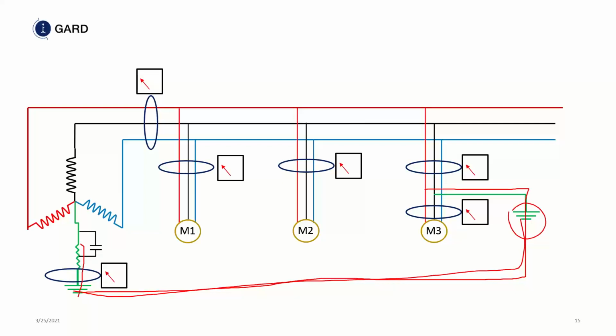That fault current only exists in this faulted path. So anywhere in that path, if we turn on the pulsing and we change the value of that resistor, we're going to see a fluctuation in the current if we put a 3-phase CT around all 3 phases of the system. We're going to follow this signature right down to the very point of the fault. As soon as we pass the point of the fault, we're going to see normal phase current. So we know that we've either passed the fault or the fault doesn't exist anymore, and we can go back and find where the fault is.